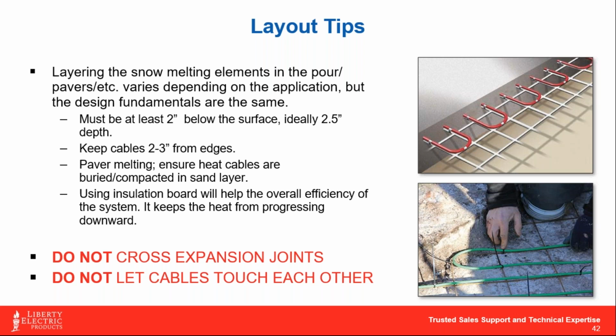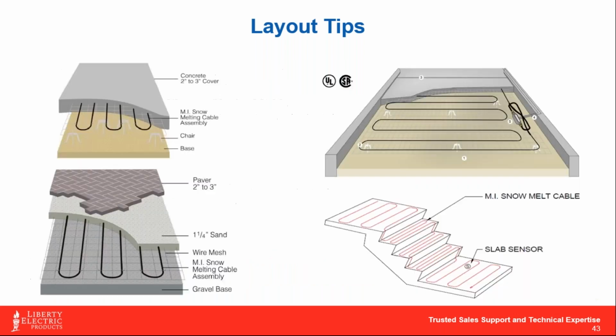One other thing: when you have an embedded sensor in the sidewalk, you do not want to get that heat cable right up against the metal can that sensor is sitting in, or else you're going to get false reads. It makes obvious sense, but it's something specifiers should put on that spec or bring to the installer's attention, because it's happened. You don't want to have to go back and correct these issues after installation.